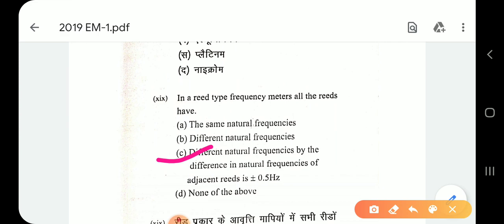The difference between two adjacent reeds is 0.5 Hz. So for example, if one reed is at 48 Hz, the next is at 48.5 Hz, then 49 Hz, 49.5 Hz, 50 Hz, 50.5 Hz, and so on.